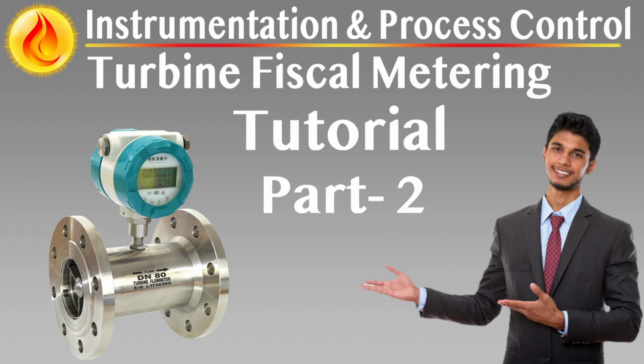Operational continuity and measurement transparency. The microcomputer-based system is the operational anchor of the Fiscal metering package. It guarantees synchronized control, high-precision computation, and secure data logging. When designed with failover logic, memory preservation, secure operator access, and protocol-based communication, it ensures not only regulatory compliance but also measurement transparency in all operating states, from normal flow to calibration, proving, and recovery.